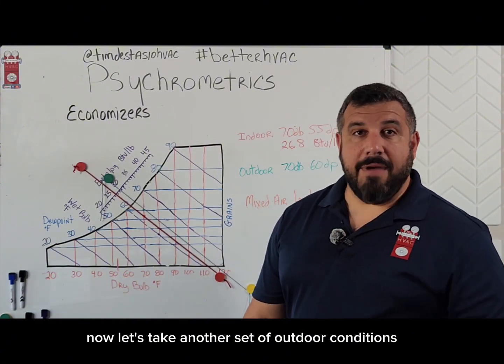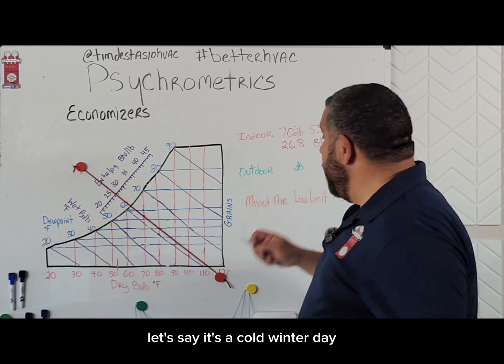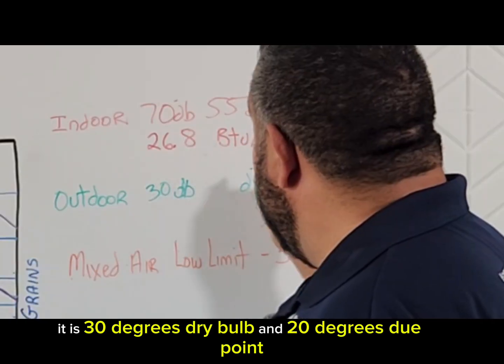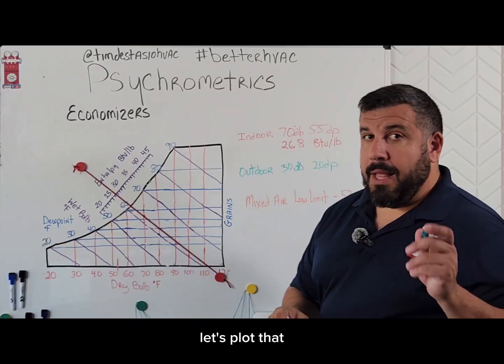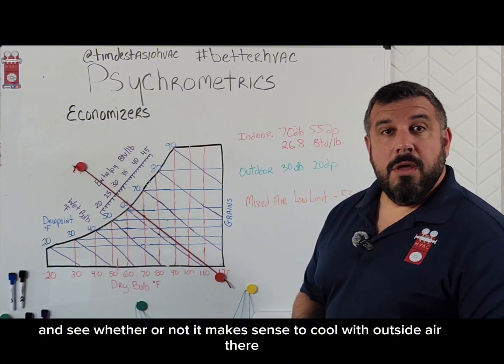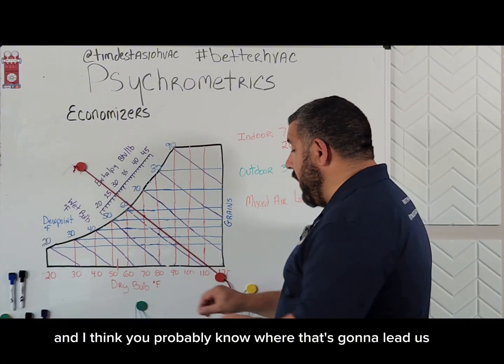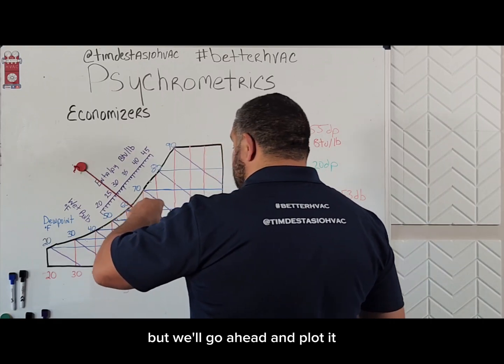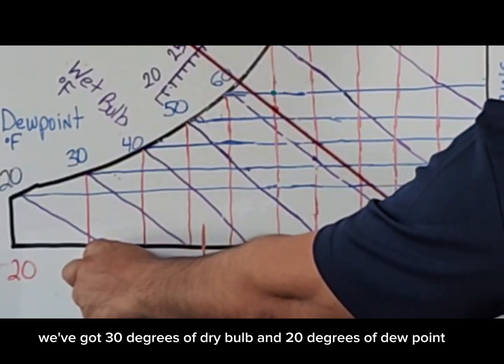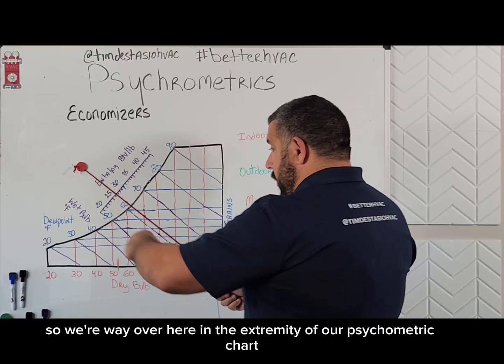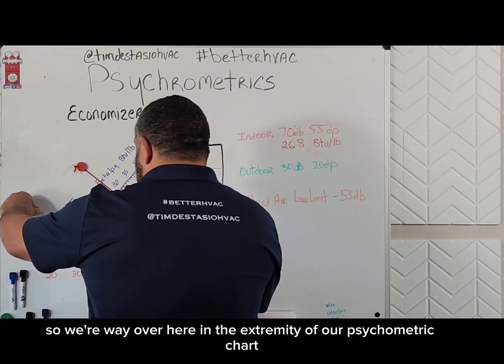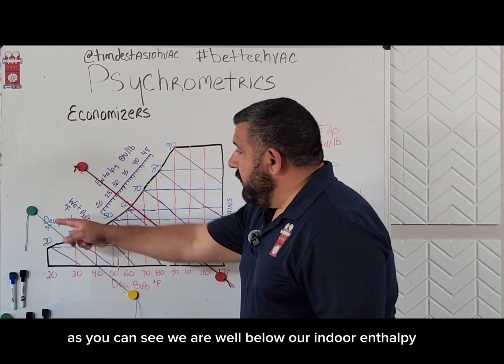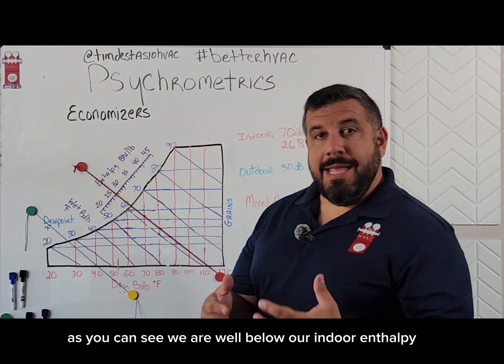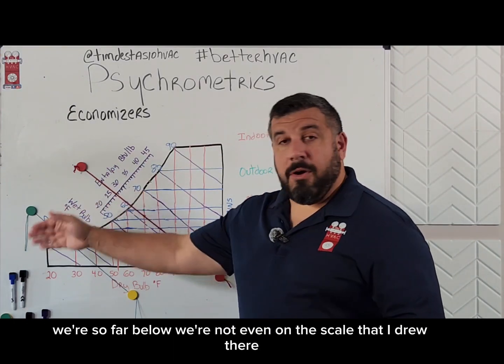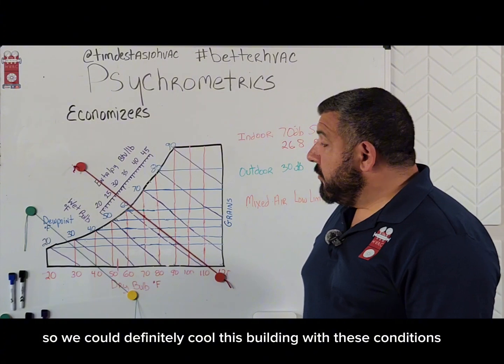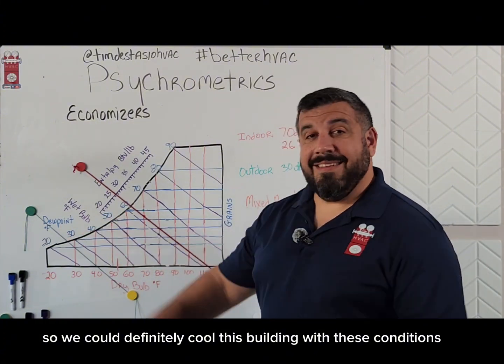Now let's take another set of outdoor conditions. Let's say it's a cold winter day. It is 30 degrees dry bulb and 20 degrees dew point. Let's plot that and see whether or not it makes sense to cool with outside air there. I think you probably know where that's going to lead us, but we'll go ahead and plot it. We've got 30 degrees of dry bulb and 20 degrees of dew point. So we're way over here in the extremity of our psychrometric chart. As you can see, we are well below our indoor enthalpy. In fact, we're so far below it, we're not even on the scale that I drew there. So we could definitely cool this building with these conditions.